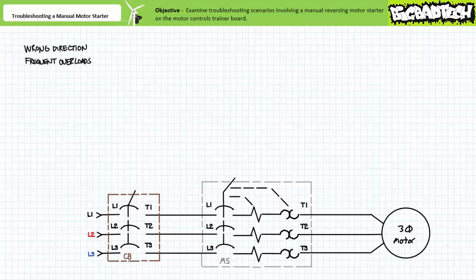Let's now examine a manual motor starter that frequently overloads. First, you must understand one of the principal tasks of a motor starter is to protect a motor from sustained overload conditions. The overload event is simply a motor starter doing its job. A technician presented with a manual motor starter that frequently overloads must treat the scenario as an investigation into the source of the overload. Very often, the answer is quite simple and obvious. The motor is overloaded.